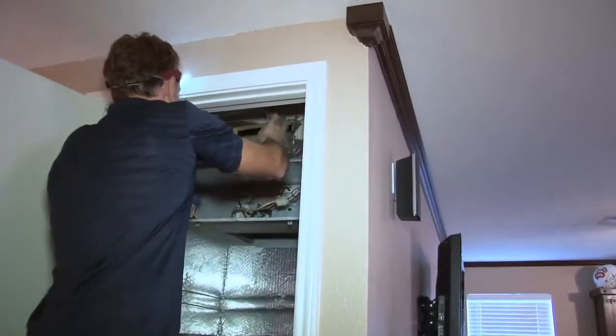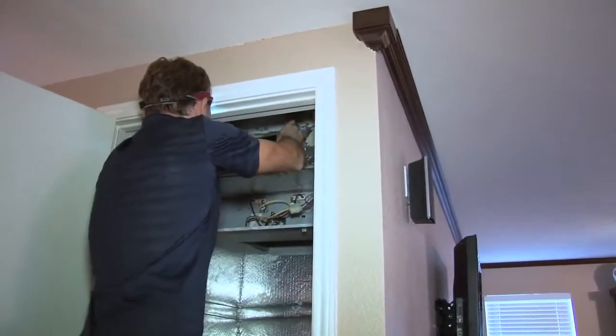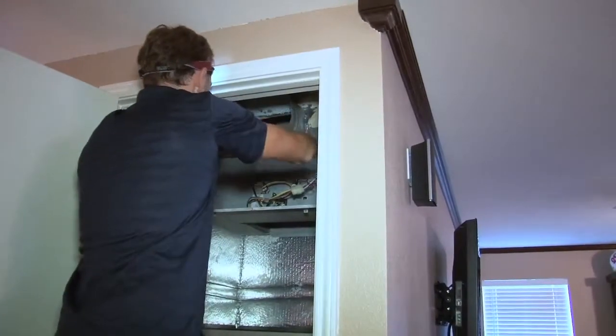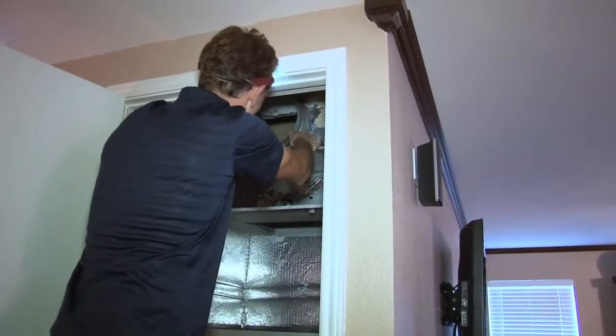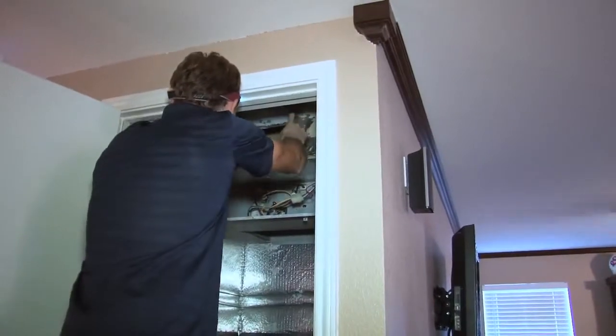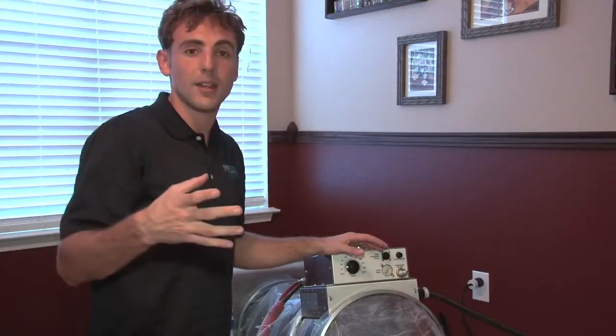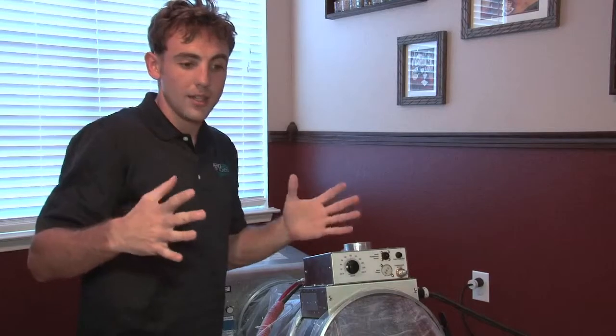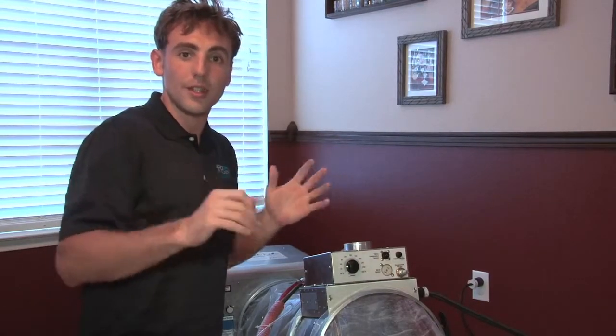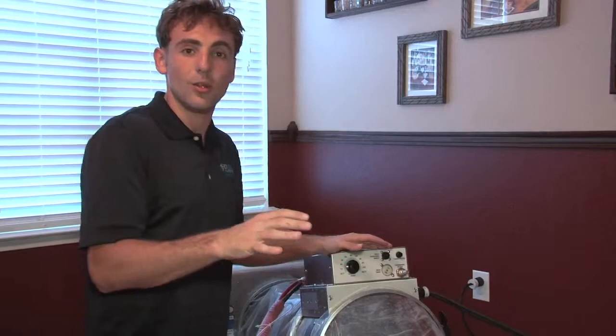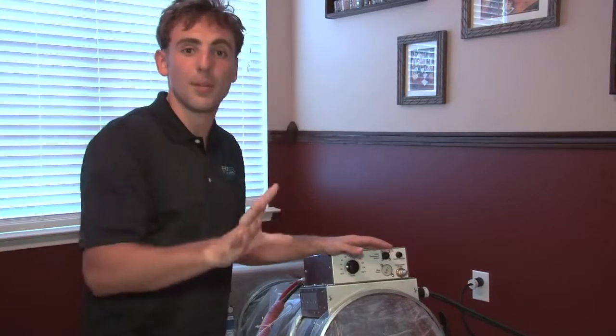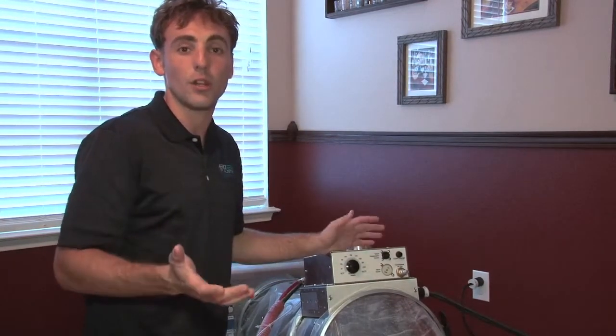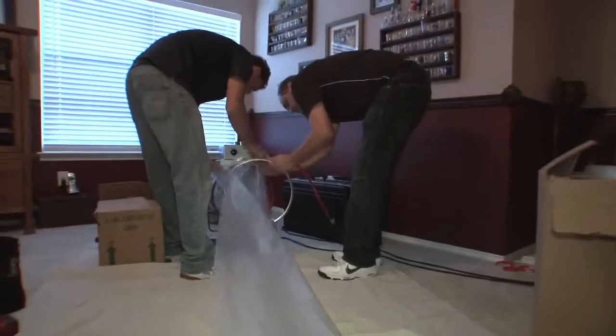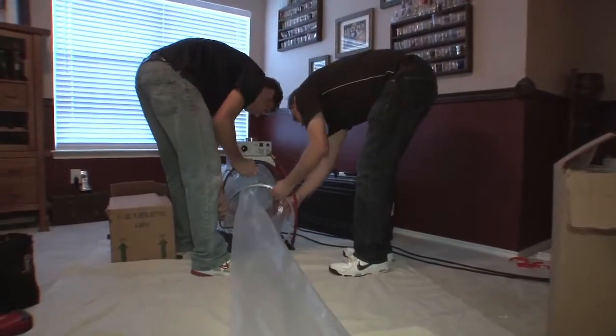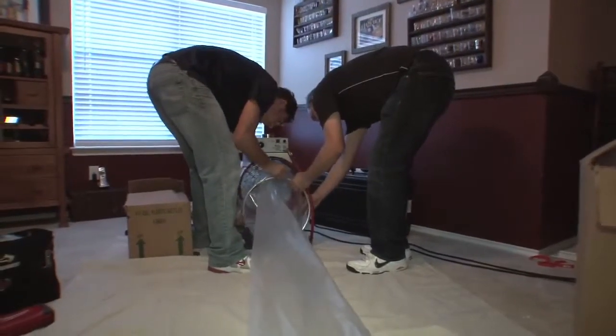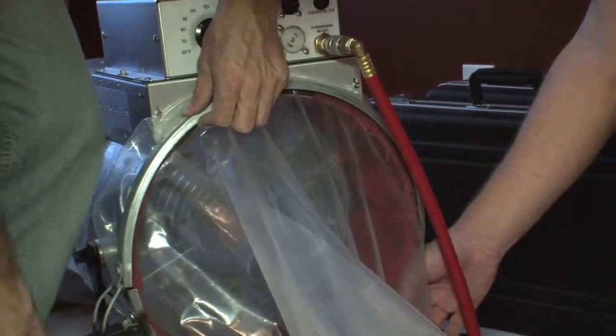In order to access your ductwork, sometimes we go through what's called a plenum. Typically plenums are basically a box that all of the other ductwork comes off of, and it's usually a box just above or just beside the air handler. This box is made out of duct board, which you can easily cut into and then easily patch back up again once you've done the job that you need to do. Once we tapped into the plenum, we put lay flat tubing and connected it to this equipment to evenly distribute the glue throughout the ductwork.